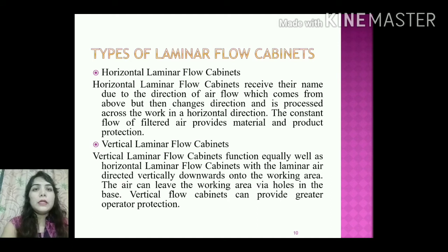Now, types of laminar airflow cabinets. There are two types: horizontal laminar airflow cabinets and vertical laminar airflow cabinets. Horizontal laminar flow cabinets receive their name due to the direction of airflow, which comes from above but then changes direction and is processed across the work in a horizontal direction from wall to wall. The constant flow of filtered air provides material and product protection.